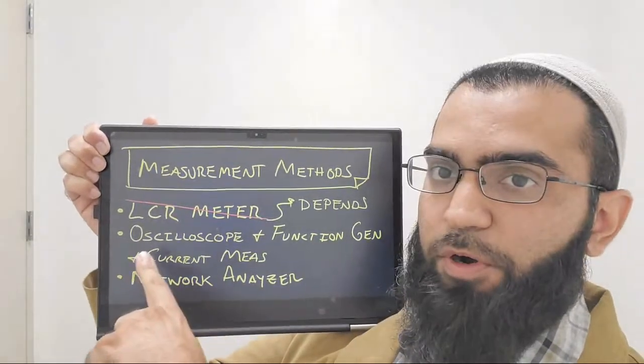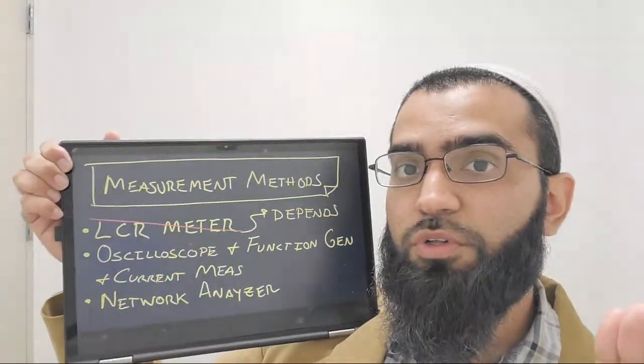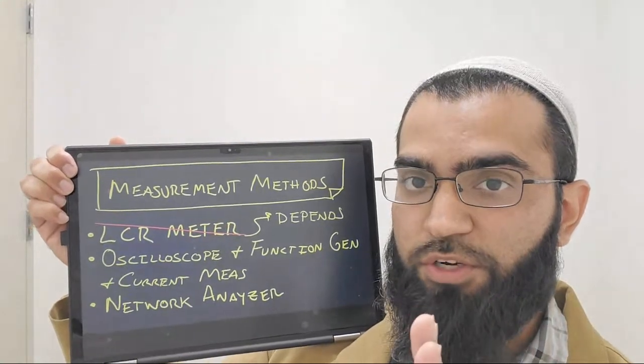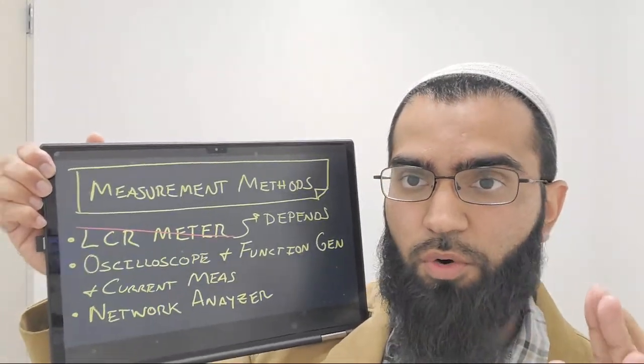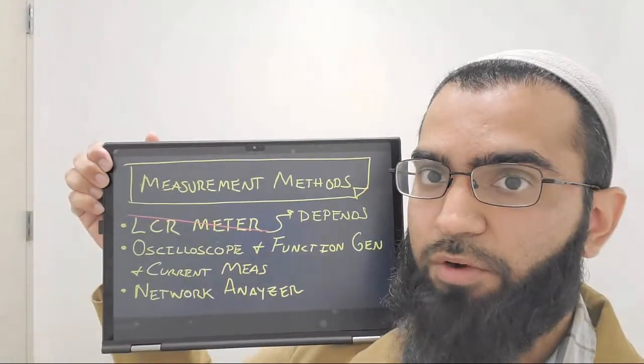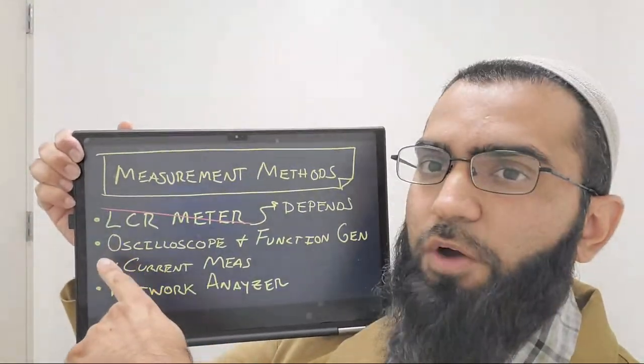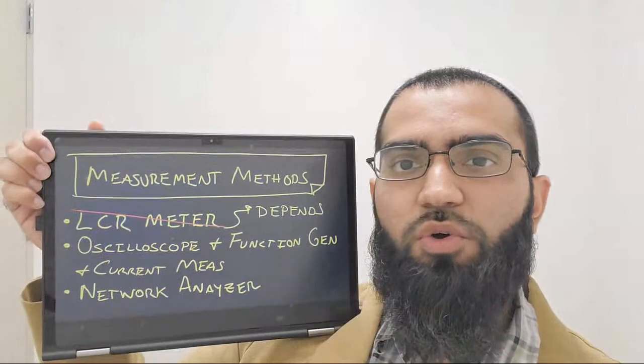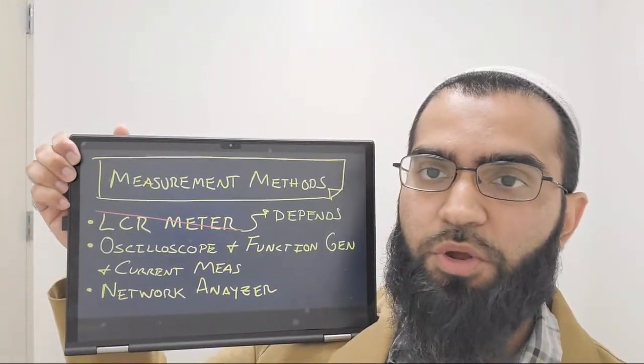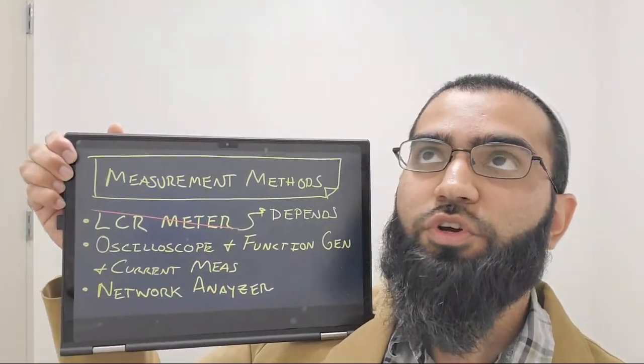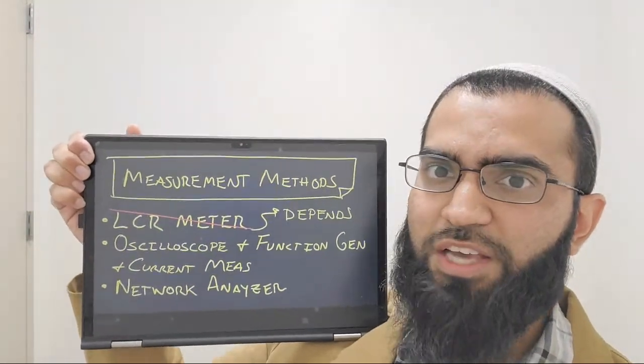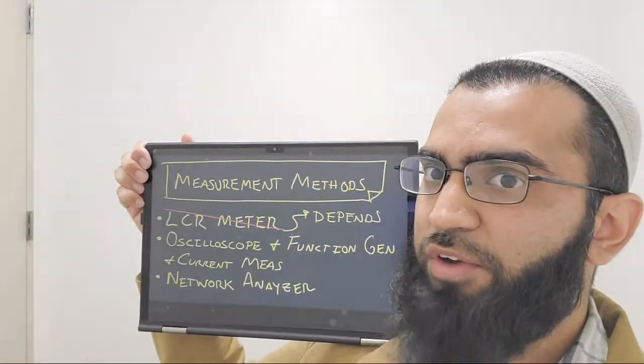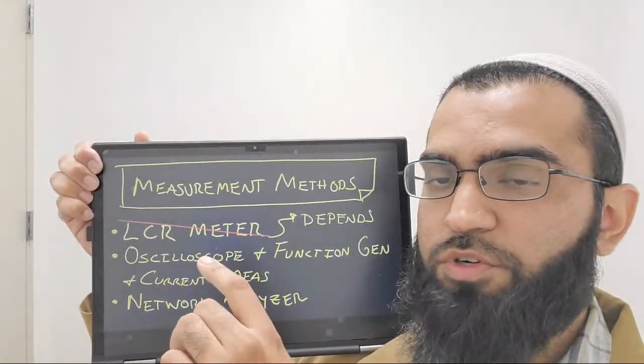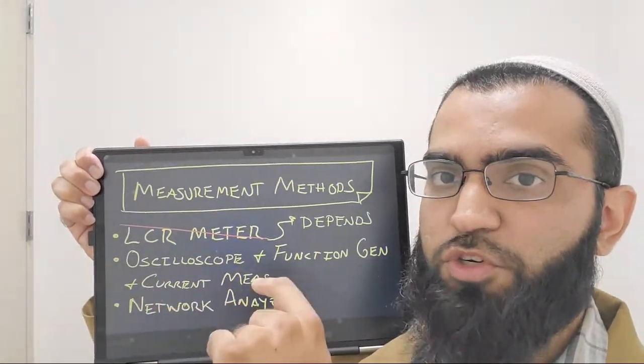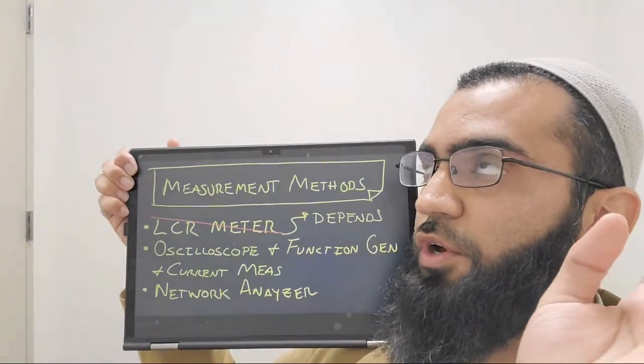So let's get on to the next part, because probably a lot of the error in electrical equipment is not from calibration. It's from user misuse or stray cabling, for example. That leads to issues. Now, if you get to the bare bones, what are you exactly doing when you measure impedance? You're measuring voltage, you're measuring current in a way, and you're measuring phase. Well, guess what? Three instruments can provide all that for you. You can use an oscilloscope to measure voltage and current, assuming you have some type of current measurement. Either it's a ground side resistor or it's a current probe.